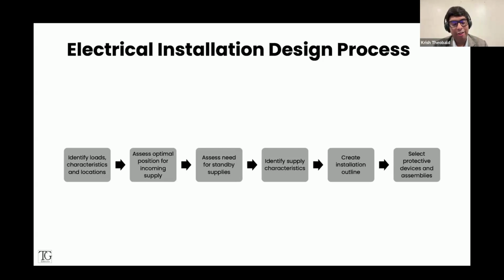If it's a LV supply, we'd have our earth fault loop impedance, we would have our maximum short circuit current, and obviously, what is the normal current for load? If it's a transformer, you have your percentage impedance, your FC, all of these things. If it's a solar PV system, similar factors. What's the maximum fault current contribution? What is the earthing arrangement, obviously, even for LV supplies?